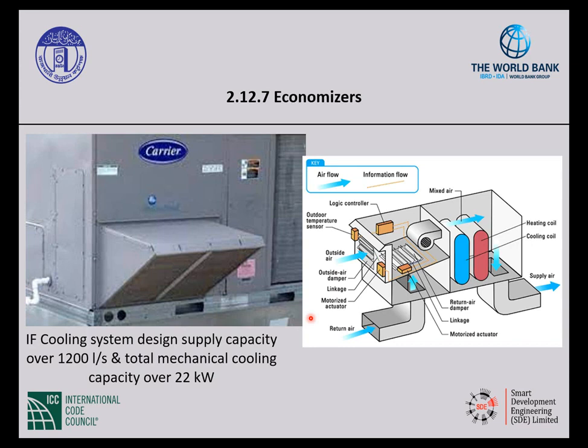When you get into this section, it says air economizers: an individual cooling fan system that has a design capacity over 1,200 liters per second or 2,500 CFM, and a total mechanical cooling capacity over 6.3 tons, shall have either an air side economizer or a water side economizer that provides 100% of the outside air design. And then it goes into some specifics. If you use a water side economizer, it must be capable of providing 100% of the system's cooling load at outside air temperatures of 10 degrees Celsius dry bulb, 7.2 degrees Celsius wet bulb, and below.